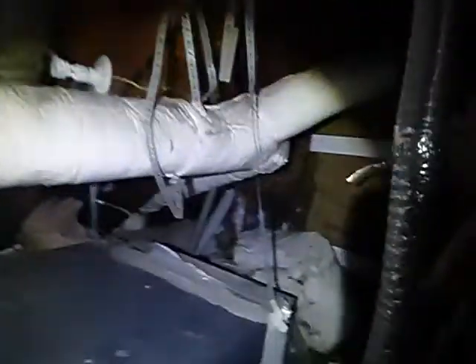This is the front of the south attic space. We do not have enough service area in front of the indoor air handler — the gas piping is in the way. It's improperly supported, suspended by perforated tape.